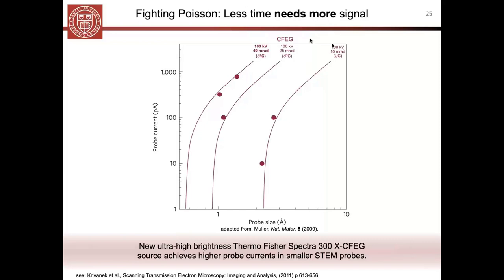If you look historically, this is data from about 10 years ago on a cold FEG, you can see aberration correction has had a huge impact on pushing this limitation. As you go from an uncorrected instrument at 100 kV, once you introduce aberration correction, you can start to open up that C2 aperture, the condenser aperture, the probe forming aperture, as you move up to higher orders of correction.